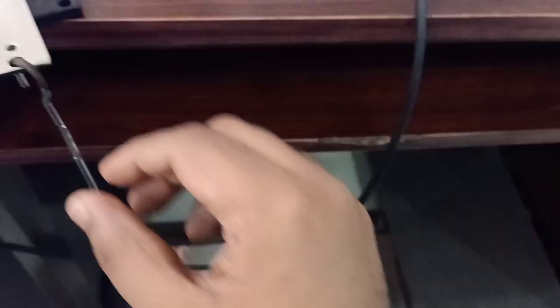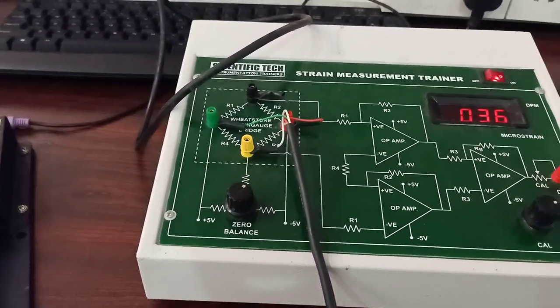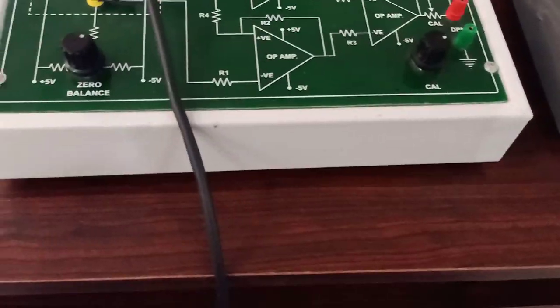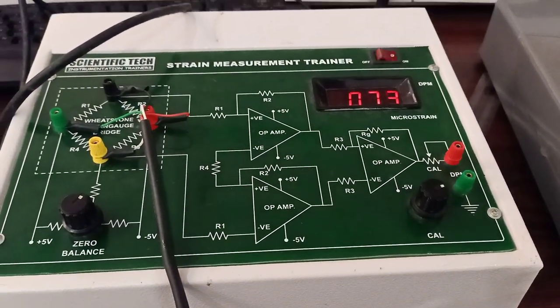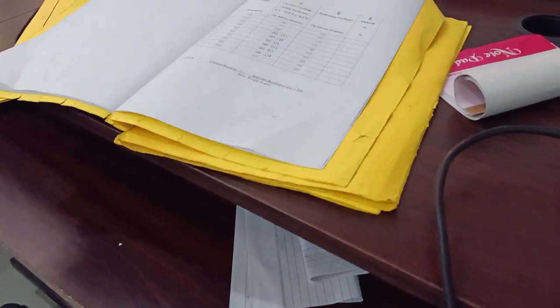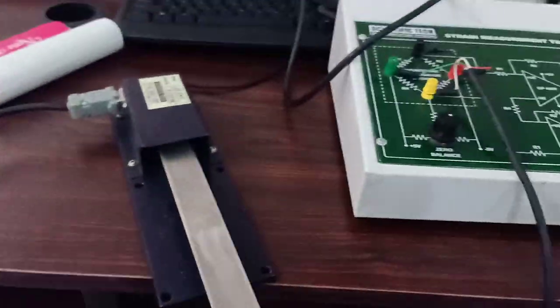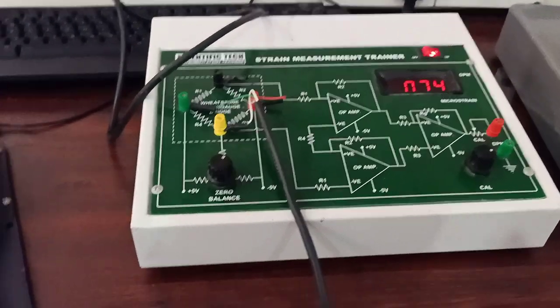I am getting 36 instead of 38 — a minor error is there. That is the beauty of calibration: by calibrating you can actually minimize this error. Now I am putting another 100 grams. For another 100 grams the output that I am getting is 74, and the actual reading is 75. So this is because of that minor error during calibration — I am getting 74 instead of 75 strain.